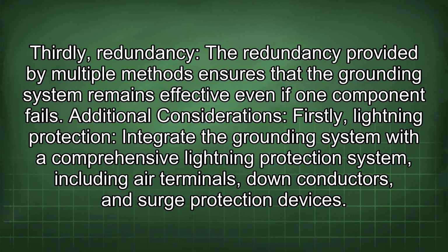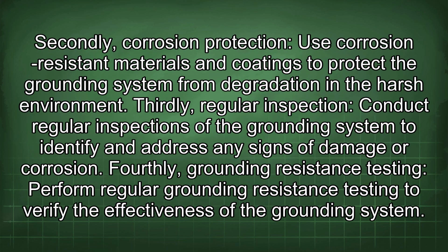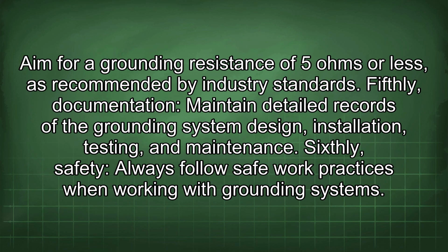Additional considerations. Firstly, lightning protection. Integrate the grounding system with a comprehensive lightning protection system, including air terminals, down conductors, and surge protection devices. Secondly, corrosion protection. Use corrosion-resistant materials and coatings to protect the grounding system from degradation in the harsh environment. Thirdly, regular inspection. Conduct regular inspections of the grounding system to identify and address any signs of damage or corrosion. Fourthly, grounding resistance testing. Perform regular grounding resistance testing to verify the effectiveness of the grounding system. Aim for a grounding resistance of 5 ohms or less, as recommended by industry standards.